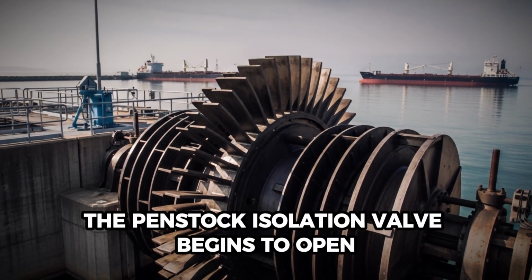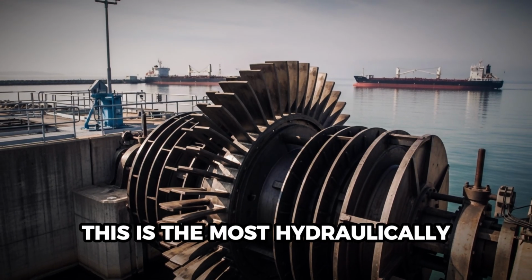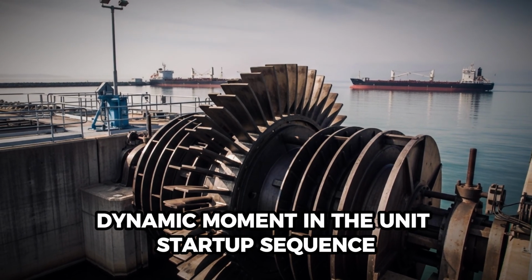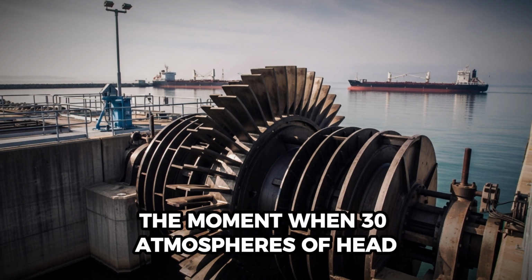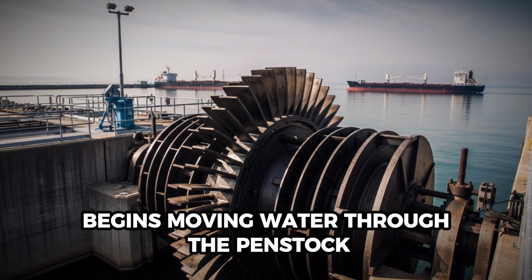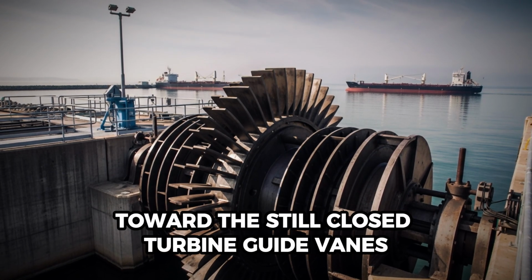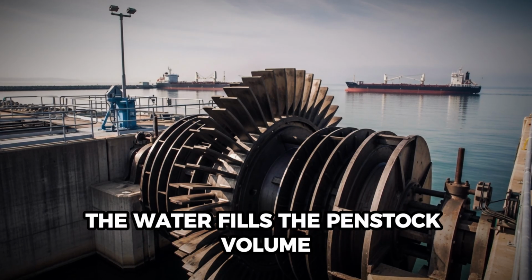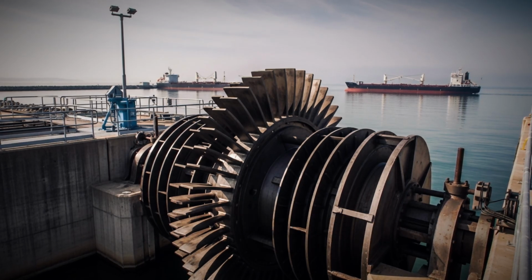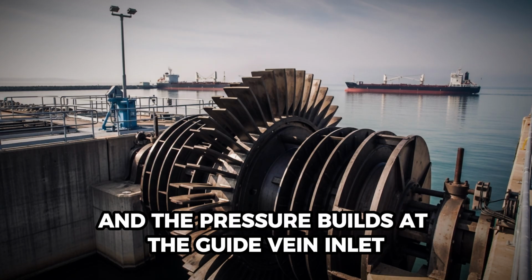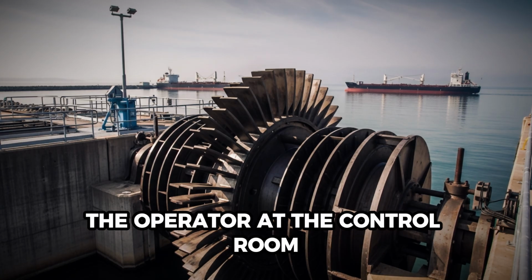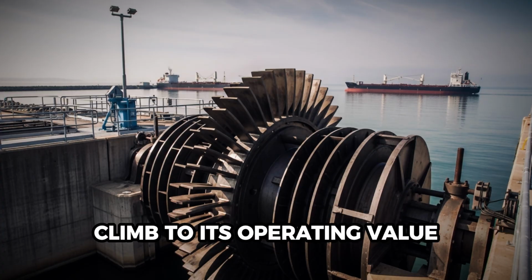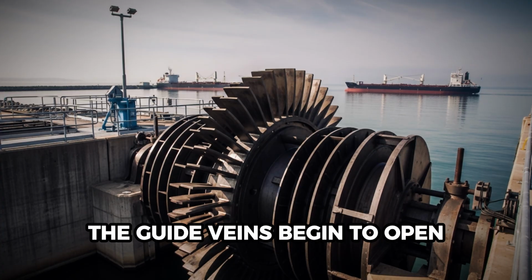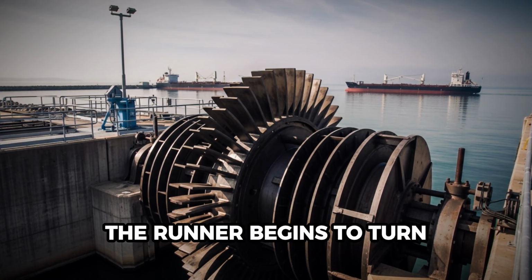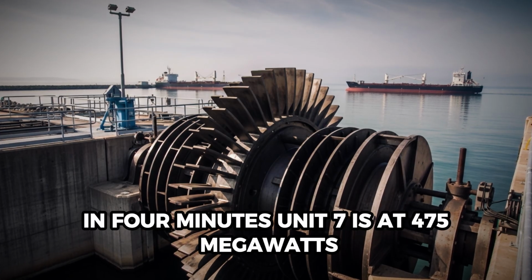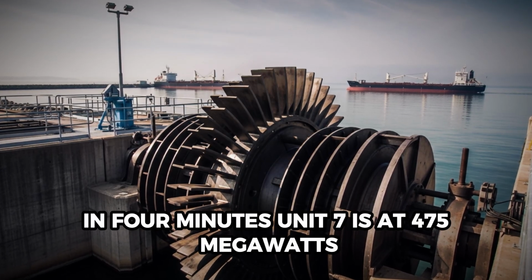The penstock isolation valve begins to open. This is the most hydraulically dynamic moment in the unit startup sequence. The moment when 30 atmospheres of head begins moving water through the penstock toward the still-closed turbine guide vanes. The water fills the penstock volume, and the pressure builds at the guide vane inlet. The operator at the control room watches the inlet pressure gauge climb to its operating value. The guide vanes begin to open. The runner begins to turn. In 4 minutes, Unit 7 is at 475 megawatts.